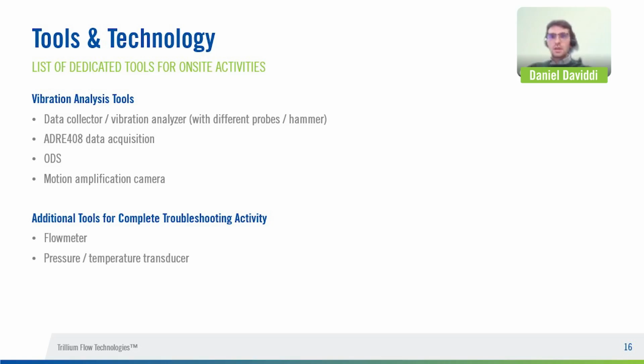Okay, as you can see in this slide, we use a dedicated tool for vibration analysis and additional tools for complete troubleshooting activities, also for the performance of the machine. As a vibration analysis tool, we use data collectors that are essential for measuring and then analyzing vibration level in the pump, providing overall measures, trend, and spectral analysis of the signal.